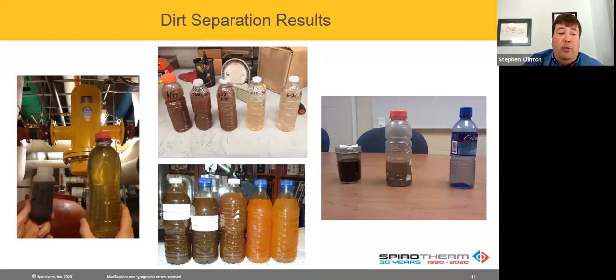So how are we different? We're not a filter, we're not a strainer. There's a difference there. What you're going to see is we're going to circulate now the water around the SPIROvent, then we're going to push the water through it. What you'll notice is the same principles that allow us to effectively remove air from the system, low velocity, low turbulence, the maximum opportunity for adhesion and collision, also happens with dirt.